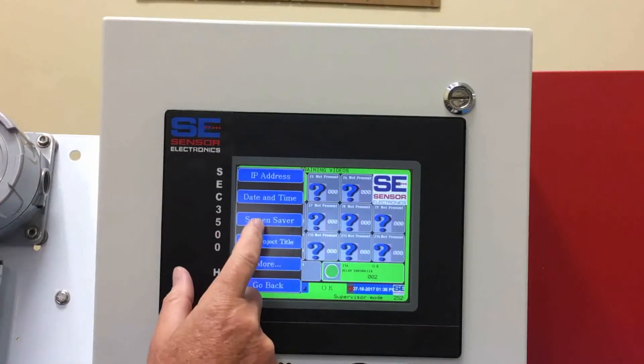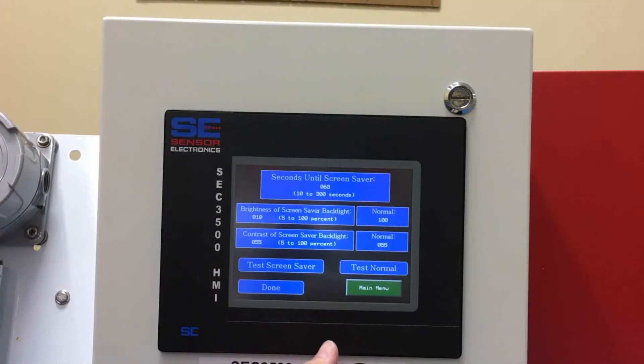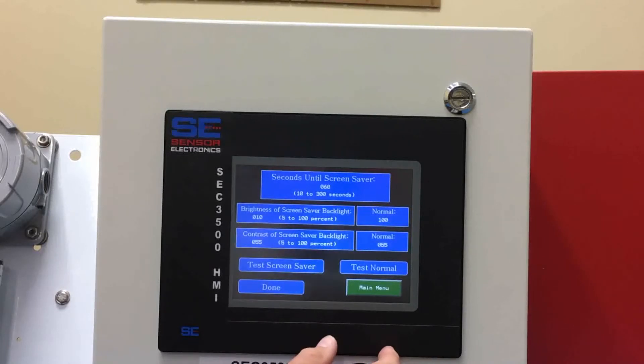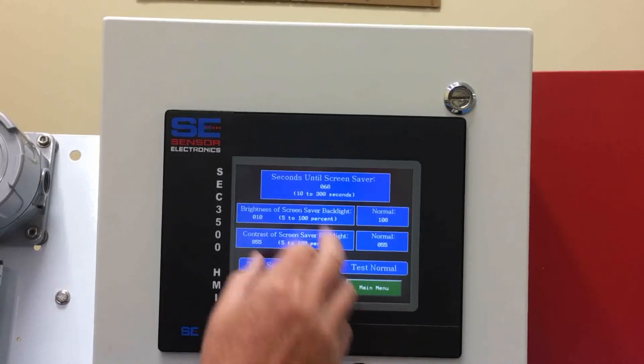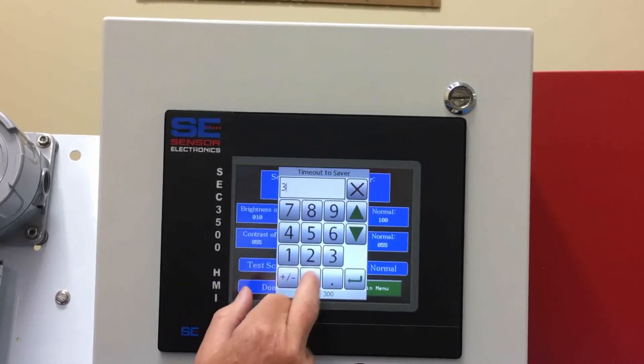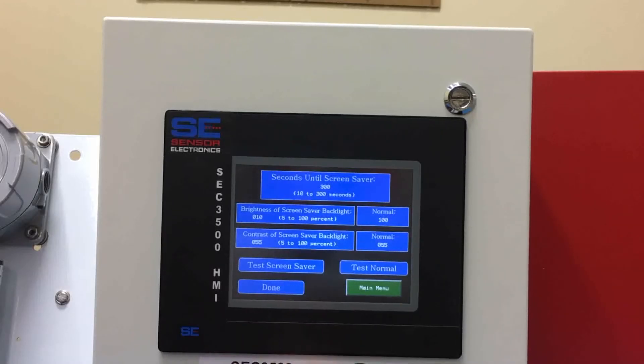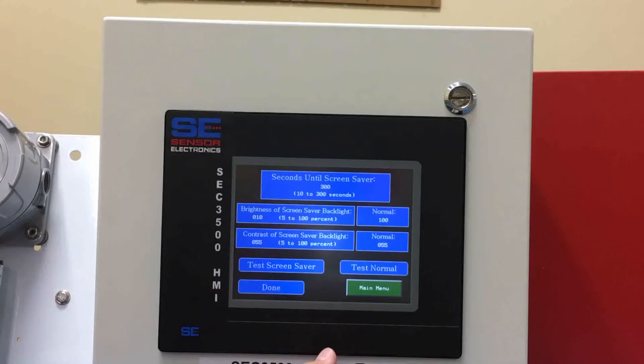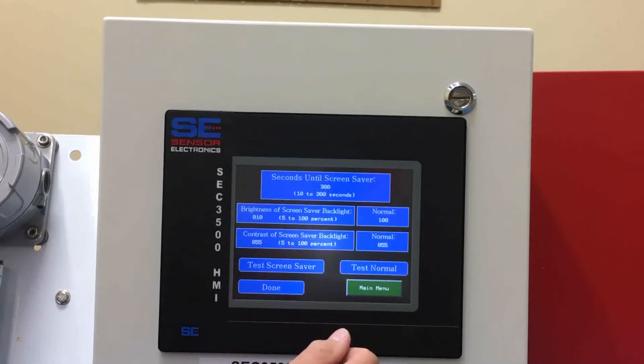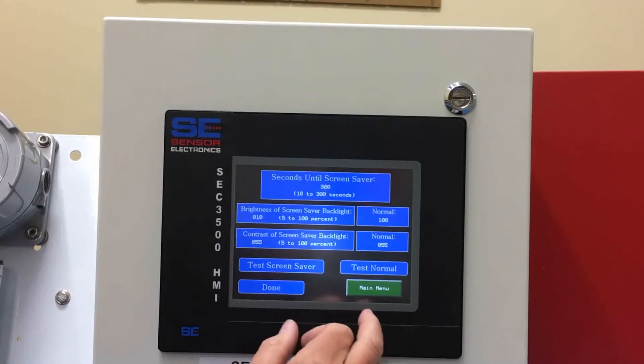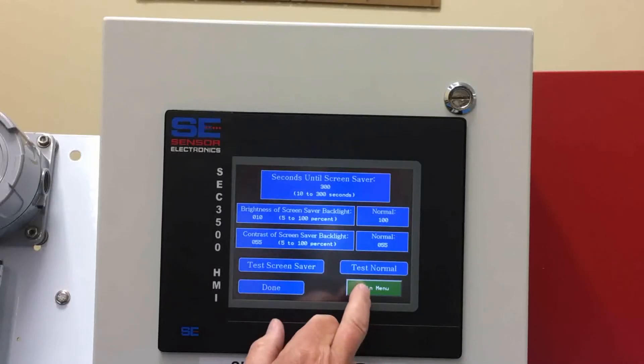Screen saver is an important one. The timeout for the screen saver — typically you'd want to max that out to 300 seconds. That will give you enough time to go through the menus and see what's going on, as opposed to having the 60-second timeout. The maximum is 300 seconds.